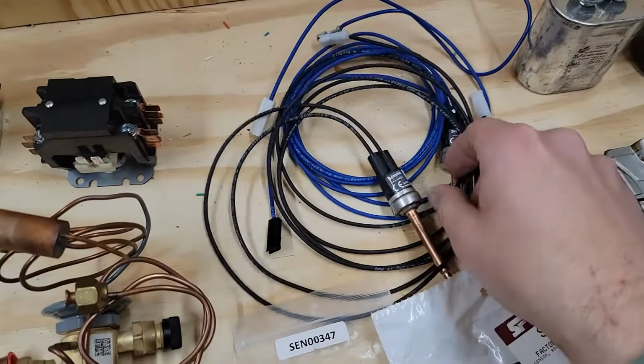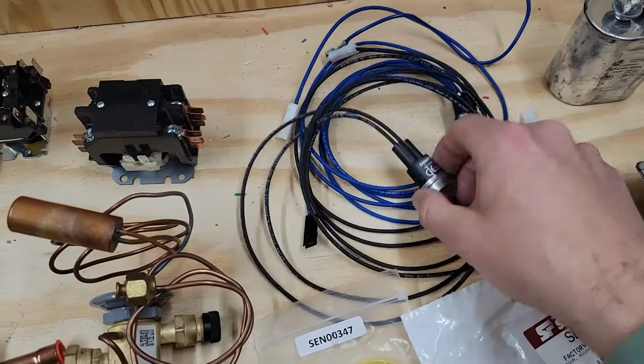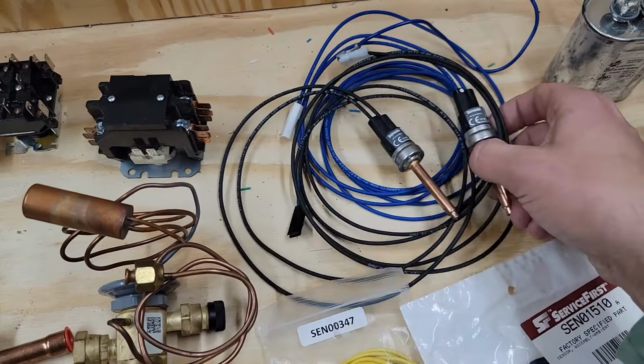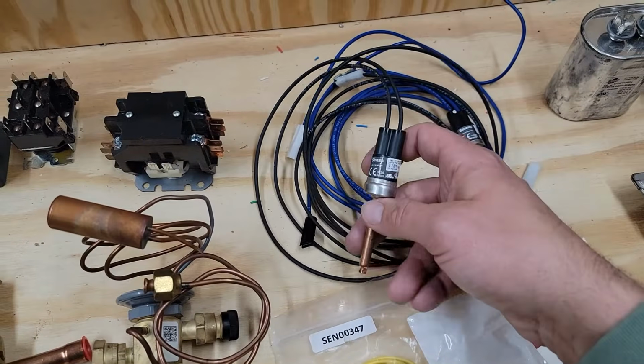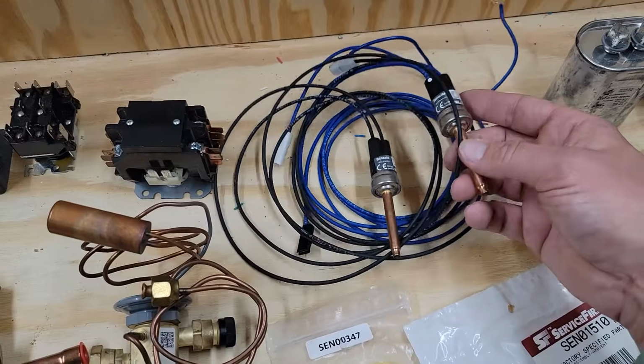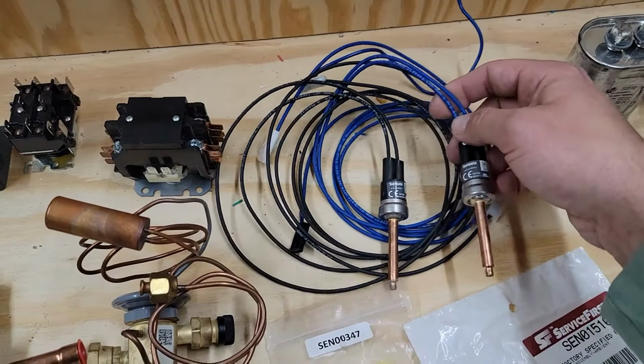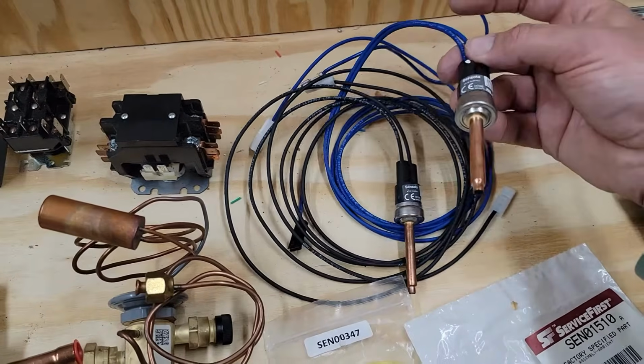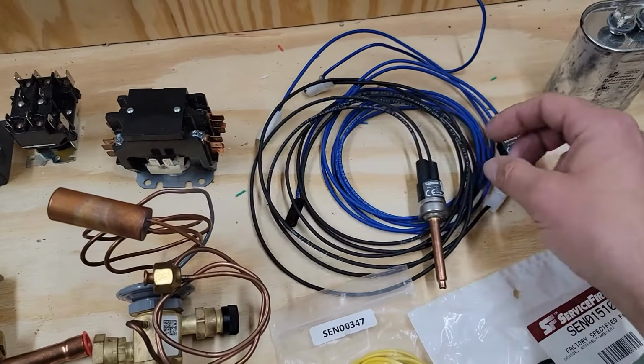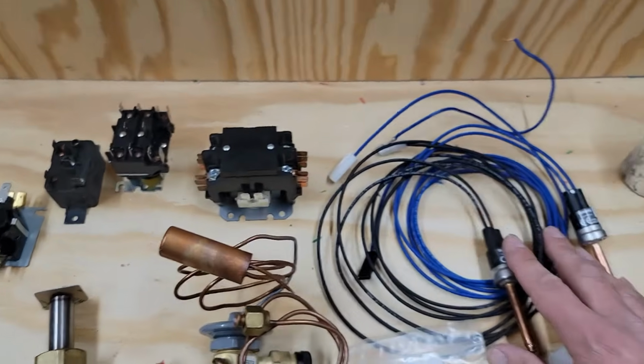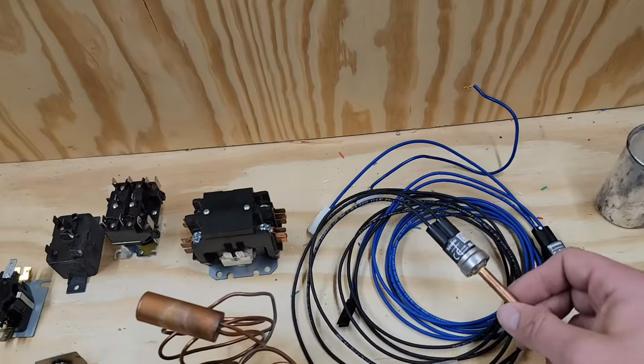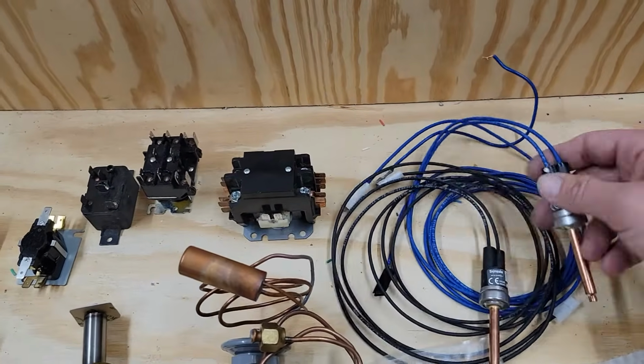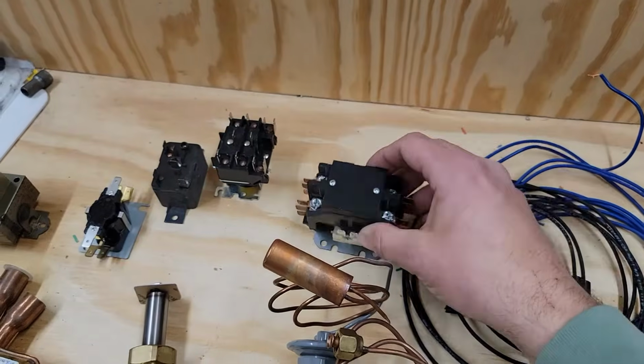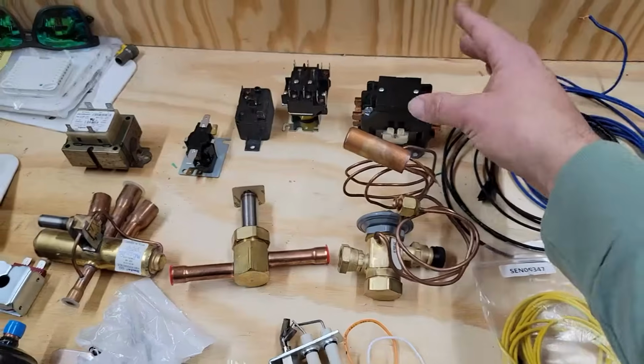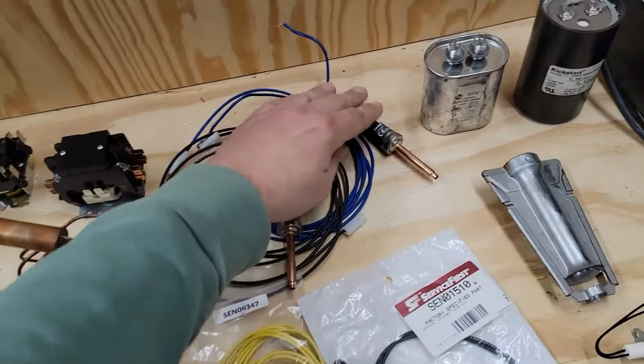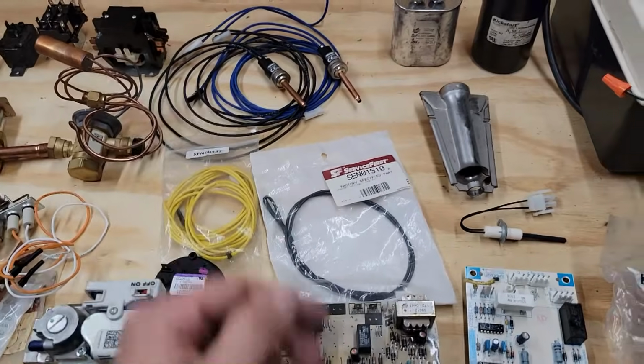So let's move on over here. This is pressure switches. We have got a low pressure switch, we've got a high pressure switch, and usually these pressure switches are closed, and this right here would open on a rise, and this right here would open on a fall. So anytime your pressure drops below 25 or probably 0, this low pressure switch would open. It's a safety, and it is in line with the coil of this contactor. So anytime these pressure switches open because either the pressure is way too high or way too low, then it would de-energize the coil of this contactor, and therefore it would turn the compressor off, and usually the outdoor fan motor. That way you're not running with no pressure or running with too much pressure. So those are pressure switches.